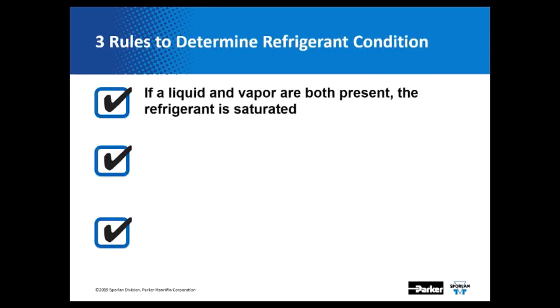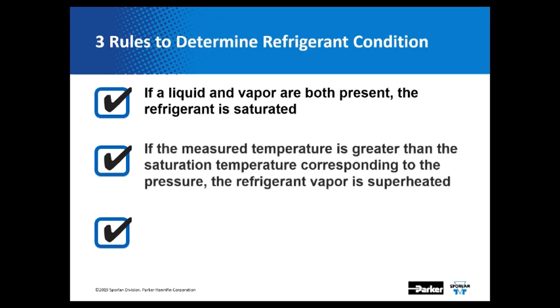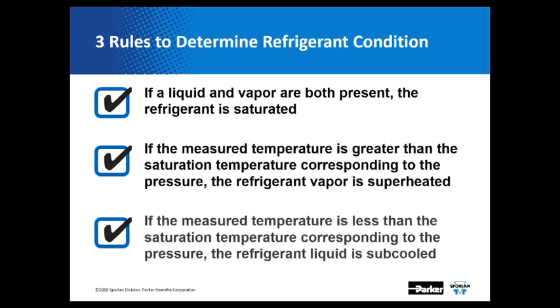To summarize the rules for determining refrigerant condition: if we have both liquid and vapor, the refrigerant is saturated — that's when we use PT charts to determine boiling and condensing points. If the measured temperature is greater than the saturation temperature, we have superheated vapor, meaning only vapor. If the measured temperature is less than the saturation temperature, the liquid is subcooled, meaning only liquid is present.